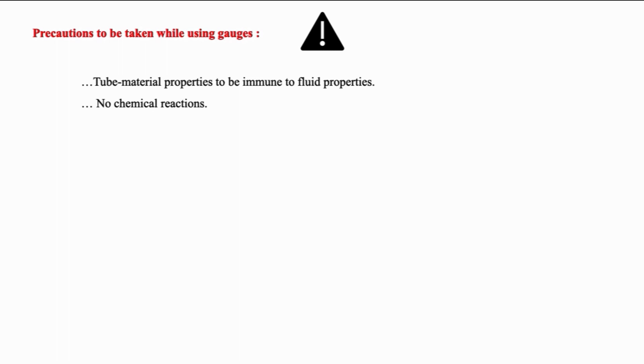Various precautions to be taken while using gauges are: tube material properties to be immune to fluid properties, no chemical reactions between the fluids and the materials of the gauge. Pressure must be within the scale value. Majority of the gauges are very sensitive to pressure surges and fluctuations. Hence, these have to be avoided during the pressure measurements.